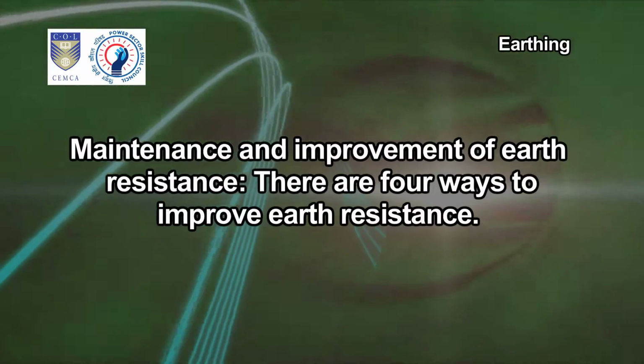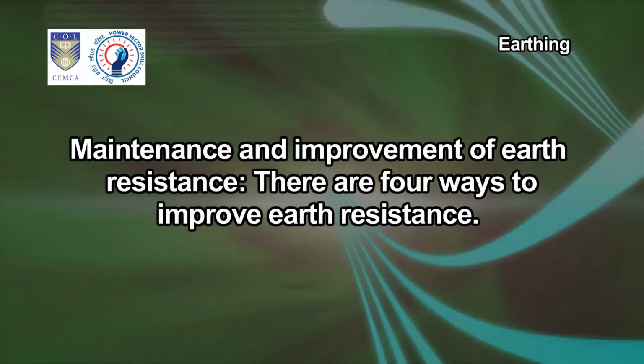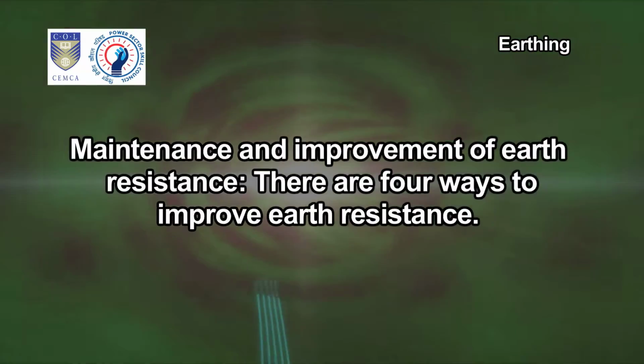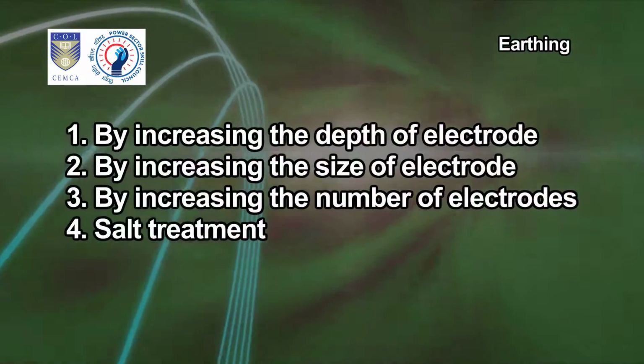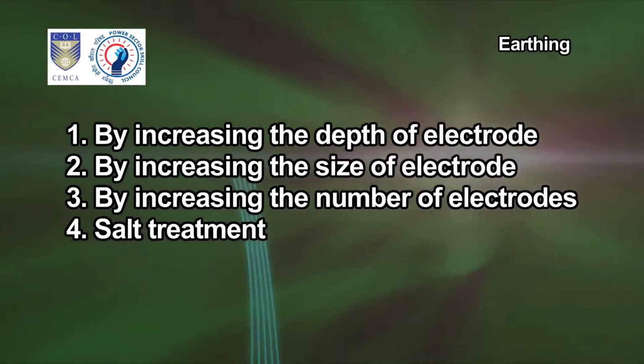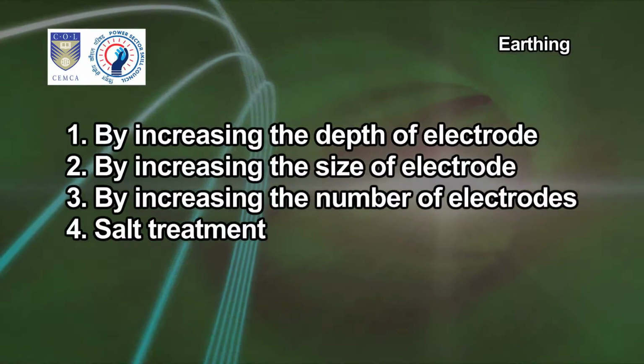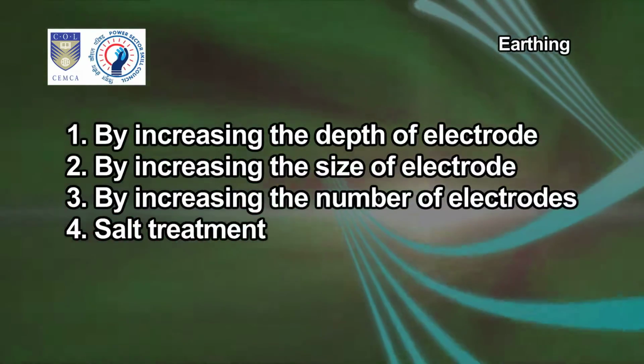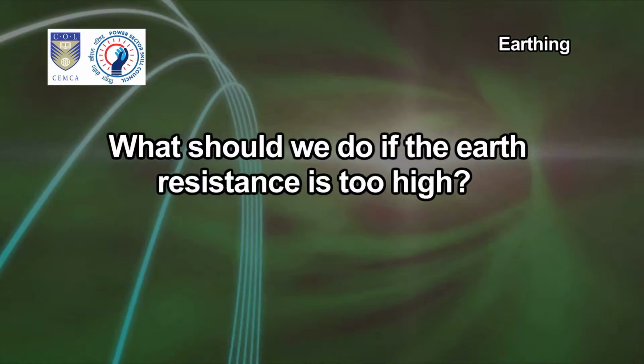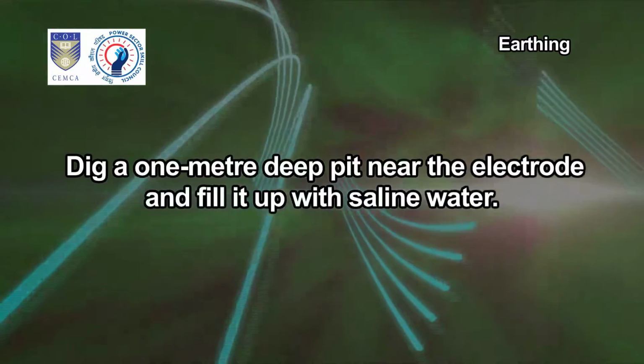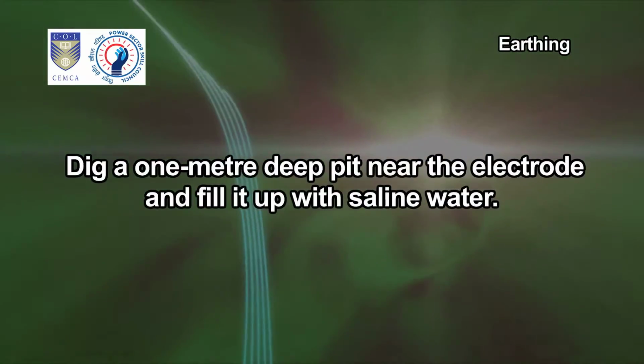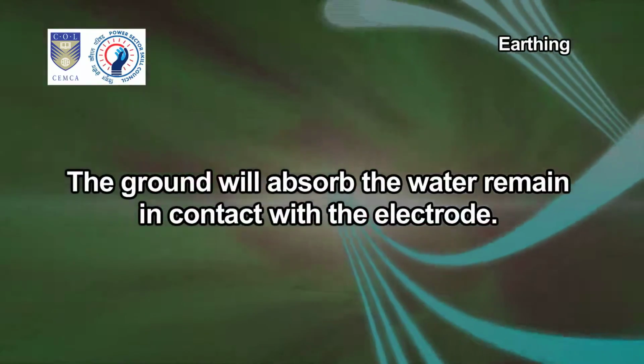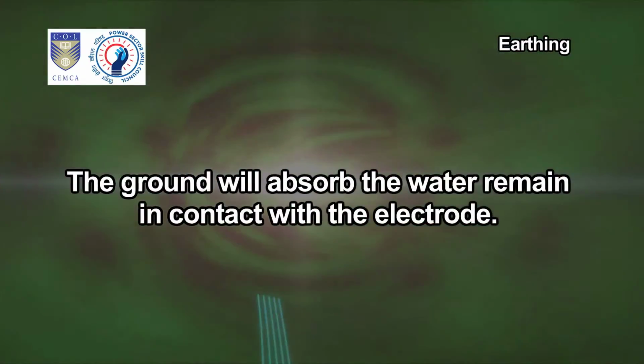Maintenance and improvement of earth resistance. There are 4 ways to improve earth resistance: by increasing the depth of electrode, by increasing the size of electrode, by increasing the number of electrodes, and salt treatment. What should we do if the earth resistance is too high? Dig a 1 meter deep pit near the electrode and fill it up with saline water. The ground will absorb the water and remain in contact with the electrode.